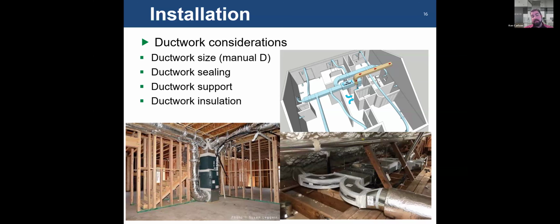At all your connections, utilize either a mastic or tape. Metal tape works at all your joint connections to try to eliminate as much leakage as possible. It's only going to hurt you. You want to get all the air, not just some of it, all the air to the rooms and not to attics, crawl spaces, basements, or anywhere else the ductwork might be. Make sure your ductwork's supported. Make sure everything's insulated. Particularly if you're in a humid climate, insulation is about preventing condensation. It's more than just preventing condensation. It's making sure that whatever conditioning you're doing, whether it's cooling or heating, that conditioned air is making it to the space at the same temperature that left the unit. Anything uninsulated, you're going to be losing or gaining temperature in the environment that the ductwork is in.